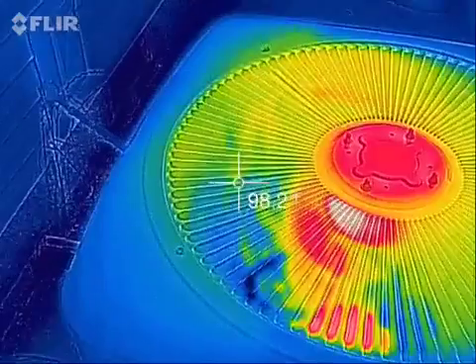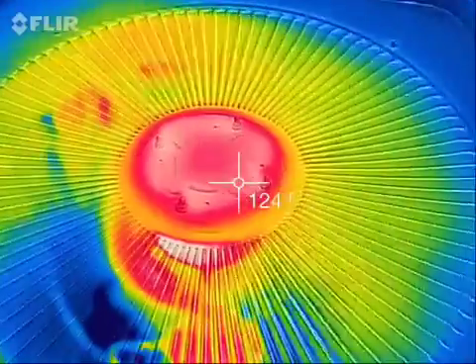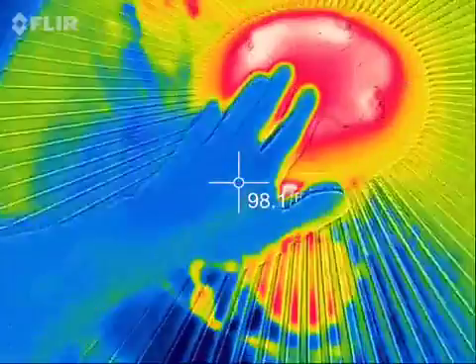It readjusted. We're at 99 on the outside edges. As we're getting closer to the motor, especially driving a fan, of course it's going to be hot — generates a lot of heat. There's my hand next to it. A lot of heat. 122 degrees versus the upper 90s.